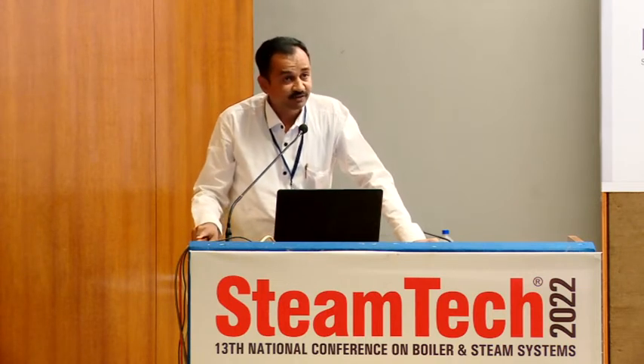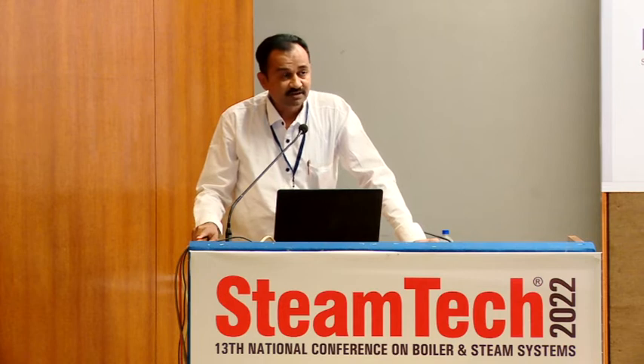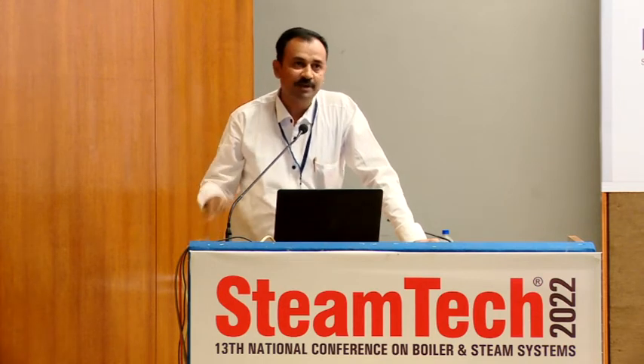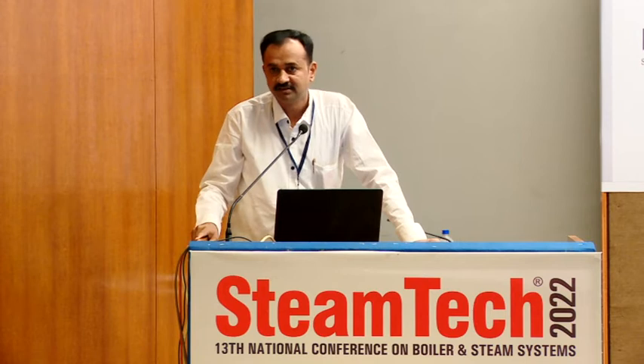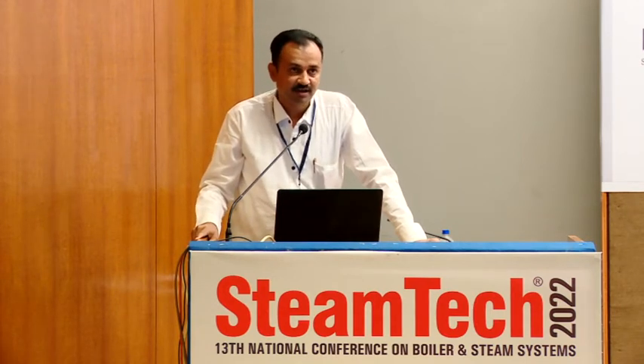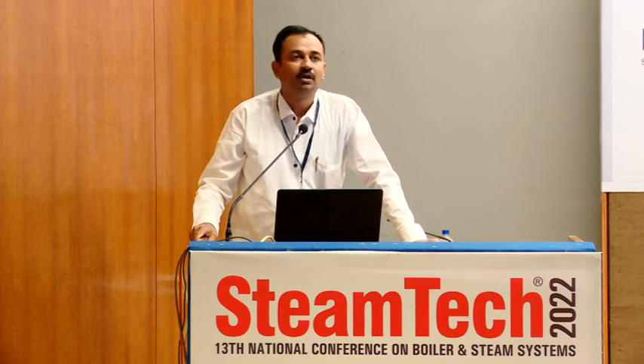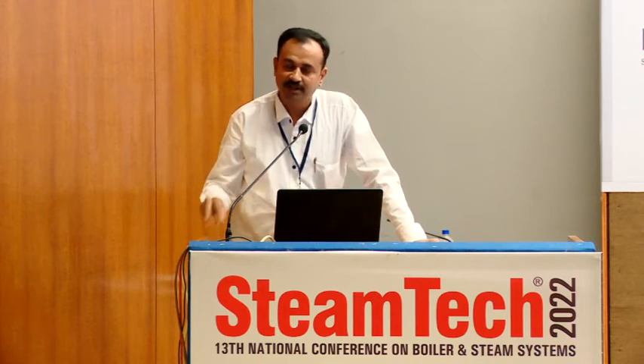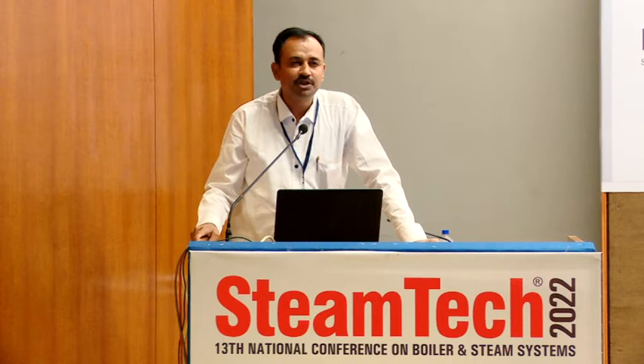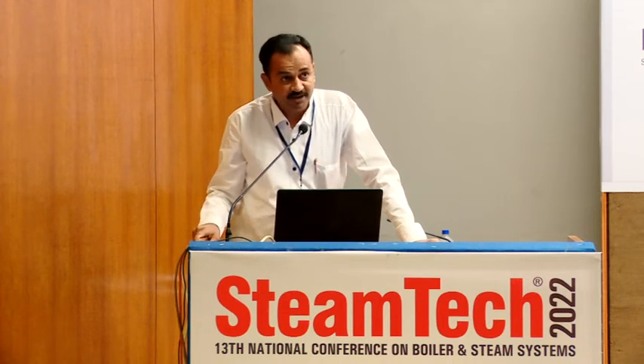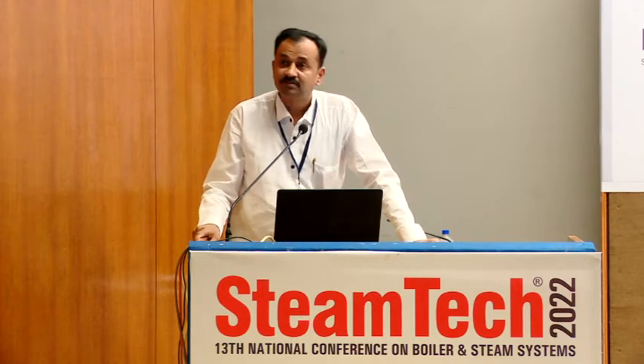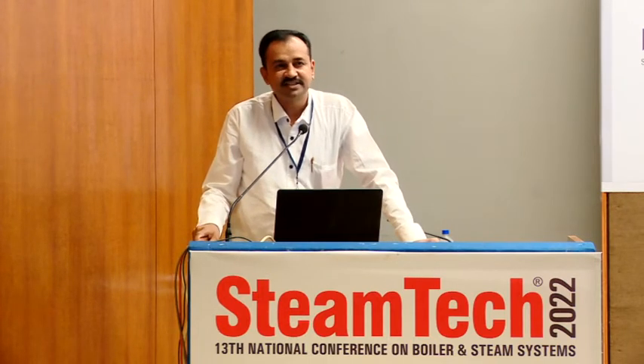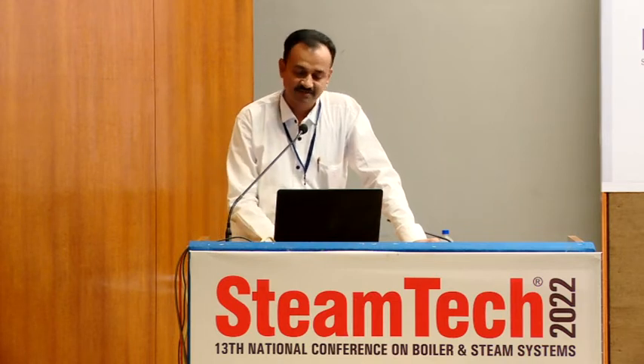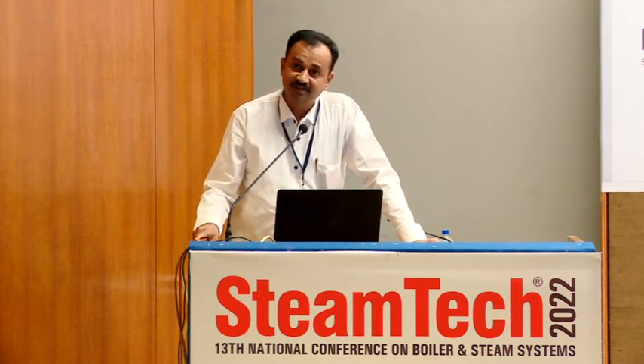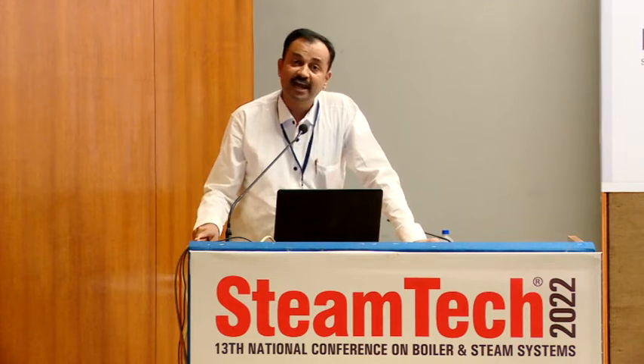Now what it says for us. If you can see, I should keep in mind what my ideal steam to fuel ratio, ideal SFC, should be. Typically for Indonesian coal, for the process industry, for the typical feed water temperature, we are able to achieve the ideal steam to fuel ratio with the best operating boiler, at plant load condition, in the tune of 6.5. But the user is only getting a steam to fuel ratio of 6. So what it says is, with a steam to fuel ratio of 6 instead of 6.5, he is losing 8%.